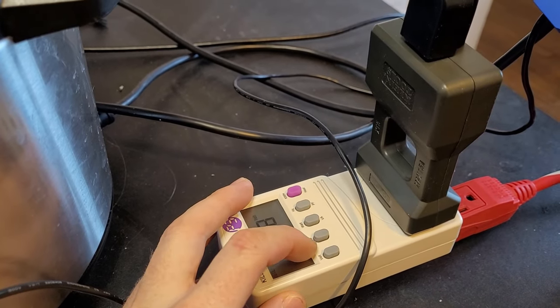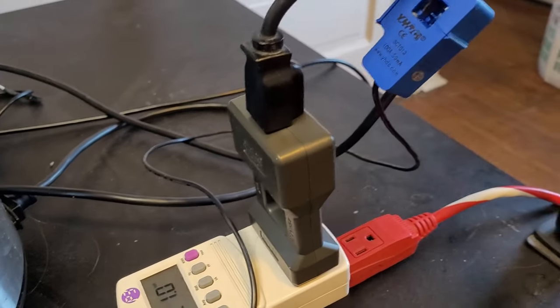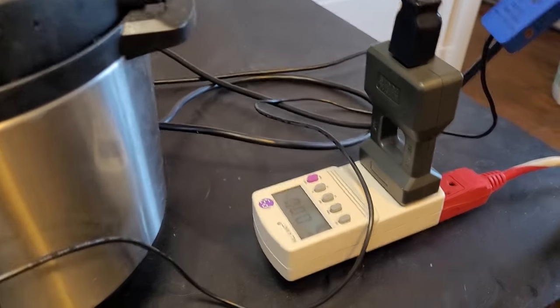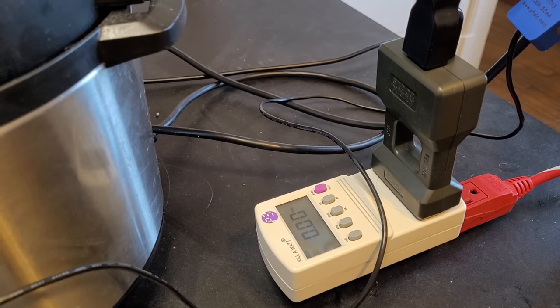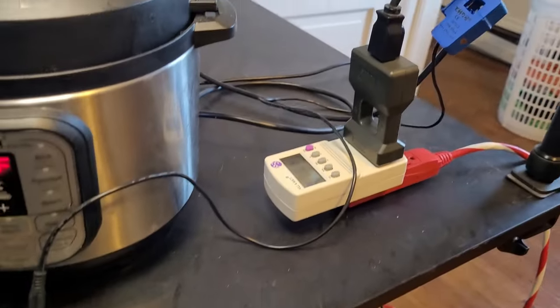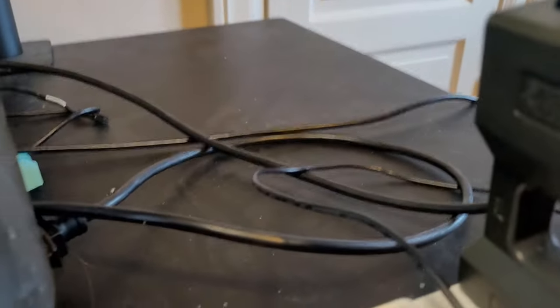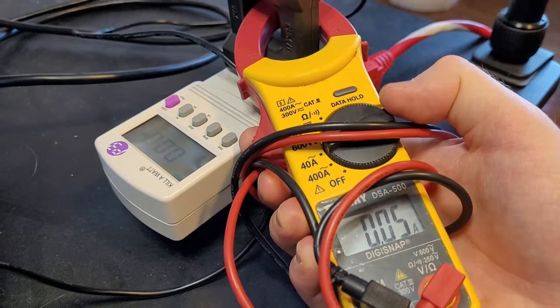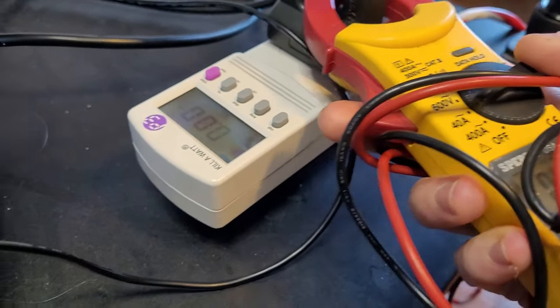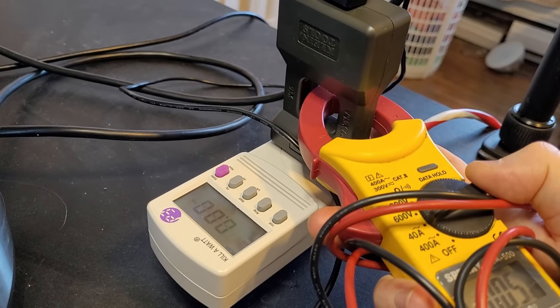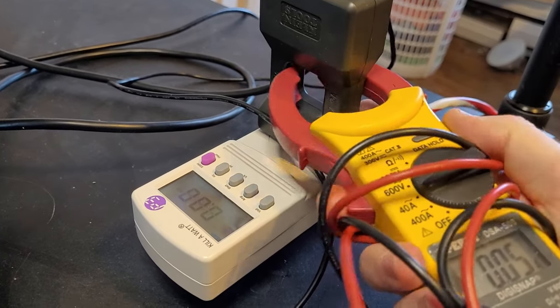This clamp over here is for 100 amps, so having something that can pull more than at least a few amps is good for testing purposes. I also have a watt meter here which is cool because it can give me the voltage, the amps, the watts, and the hertz of the system. What I would normally do is you put it on amps and you would have to compare what you got on the screen to what the meter is working with. I got this device here which allows me to put on one of these clamps and then I can measure the amperage, so I could test to make sure it was working. This one specifically is designed just to do times 10.